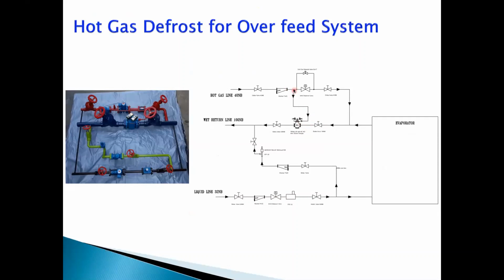Gas powered valve means hot gas which has been fed into the evaporator is partially used to operate this valve. So this valve will not operate on a typical pressure drop across the valve, but will operate by the external hot gas, like we have pneumatic valves in the process line. This is a valve which operates through the hot gas available in the plant. So no extra energy is required.